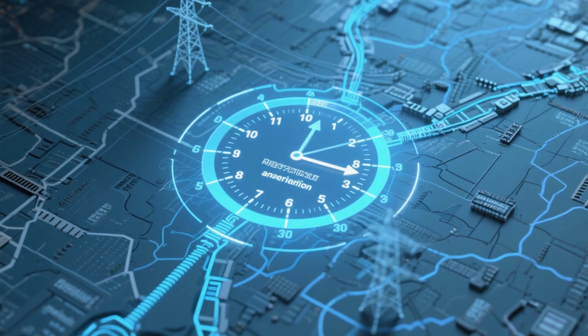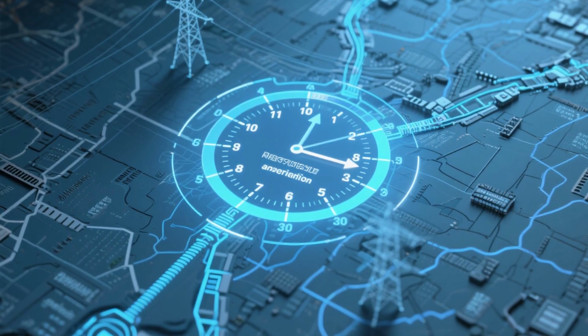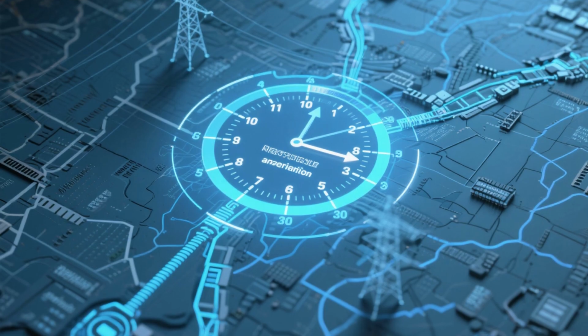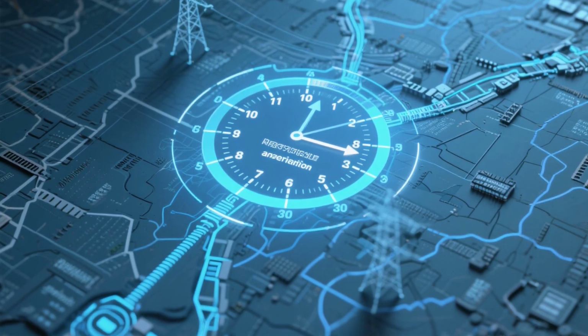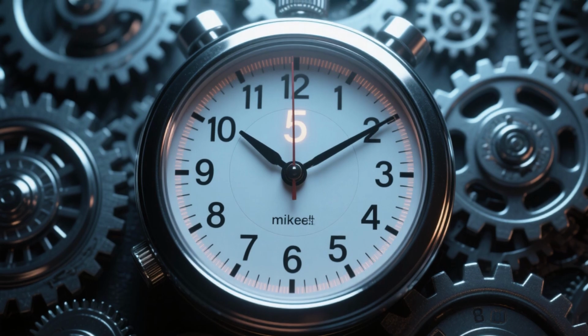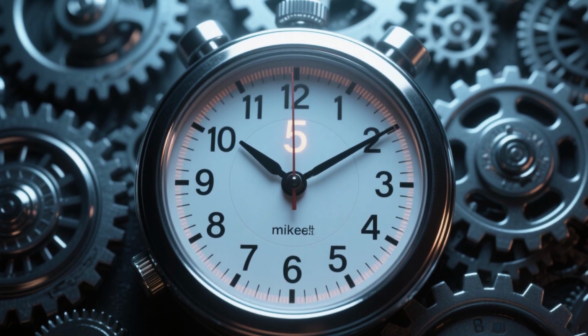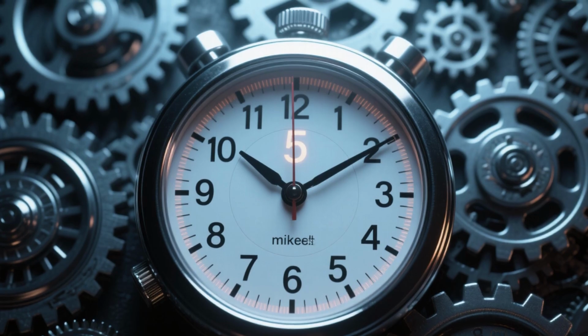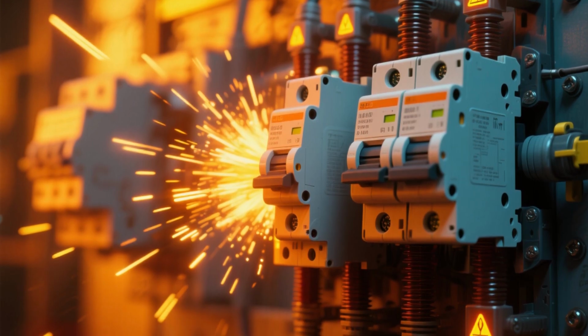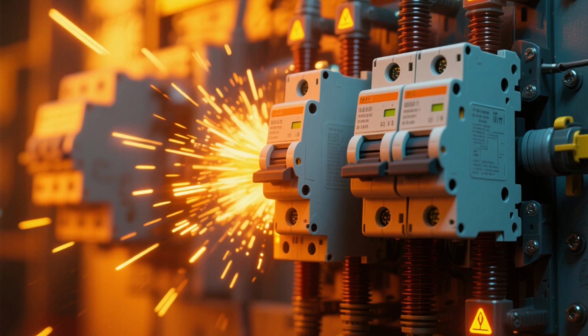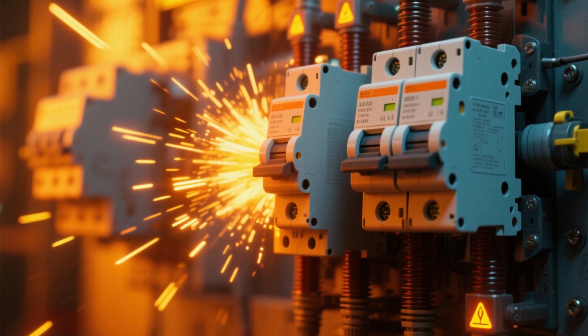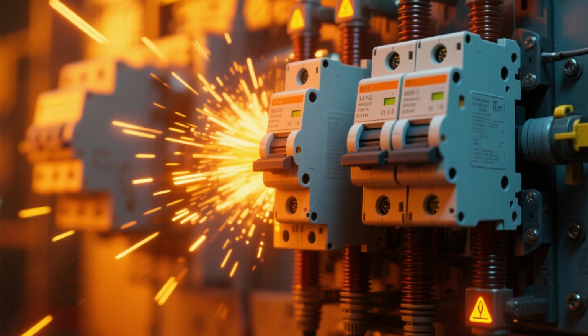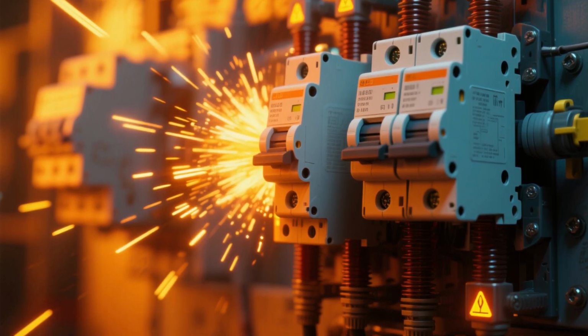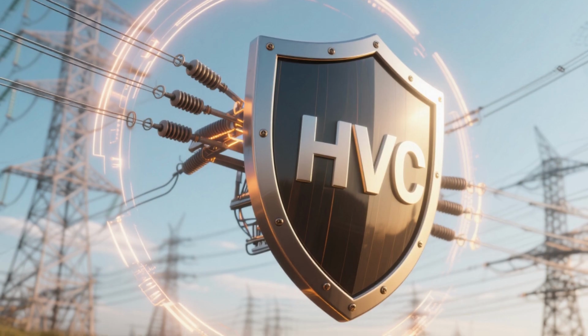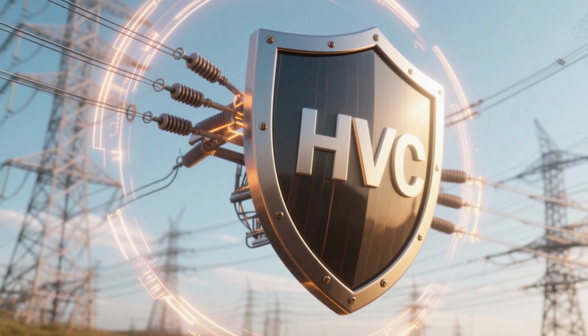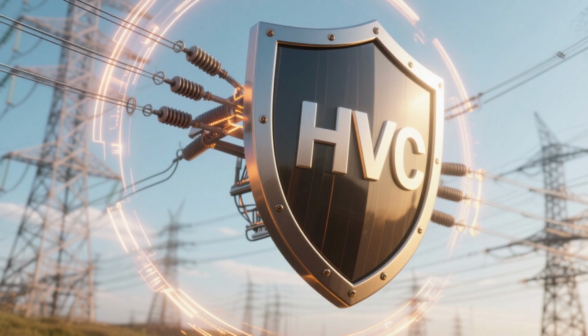By measuring the arrival time of the wave and sometimes the polarity of the initial wavefront, the system can not only detect that a fault has occurred, but also get a good estimate of its location. This time domain analysis is incredibly fast, often identifying a fault within just 2 to 5 milliseconds. This rapid detection allows circuit breakers to open and isolate the faulted section before the fault current rises to dangerous levels, protecting expensive equipment and preventing system-wide instability. The elegance of the traveling wave method lies in its intrinsic speed, making it an indispensable first line of defense for long HVDC lines.